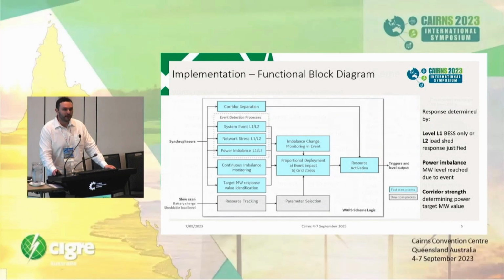This is the functional block diagram of what I described. So there are two tasks running. There's the fast scan task, which is executed every 20 milliseconds, and that has the event detection processes built in, and then there's a slower scan task, which is an interface to ElectraNet's EMS, and that's getting data on the battery charge, the sheddable load level, and the generators that are online to calculate the inertia level.